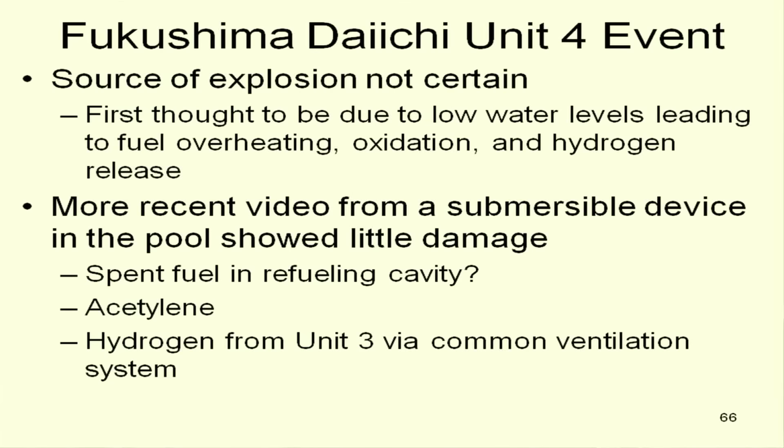Okay. The first thought was that it was due to low water levels in the pool, that the spent fuel storage pool was leaking someplace. The fuel had come uncovered. The fuel pool was crammed, with a whole core of not very old fuel. The water level went down, the fuel started to oxidize and the cladding burst, the same thing that happened in the cores of the others, just a bit more slowly, and the hydrogen had evolved and it went bang, okay?